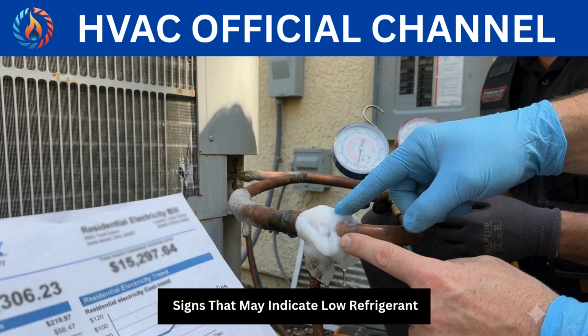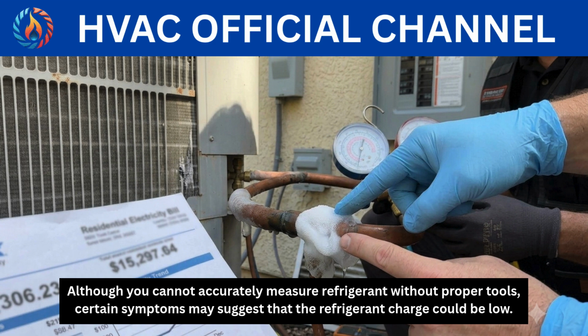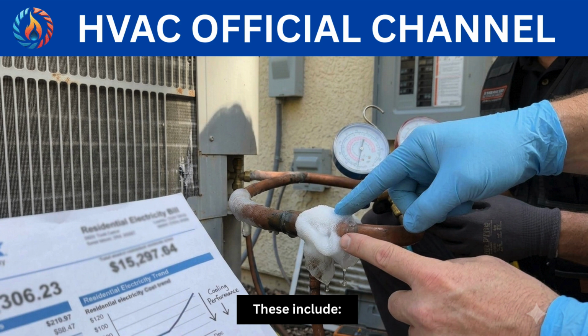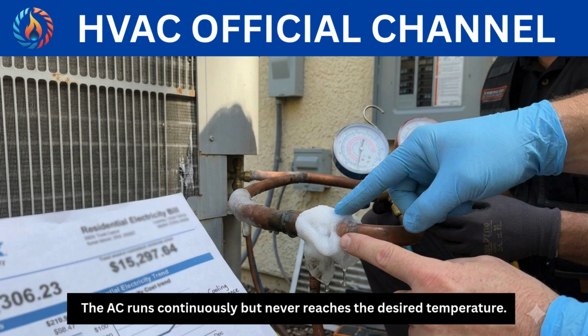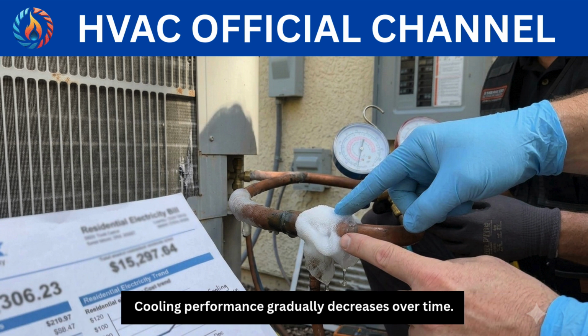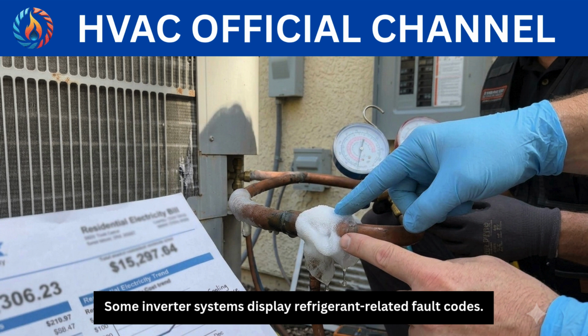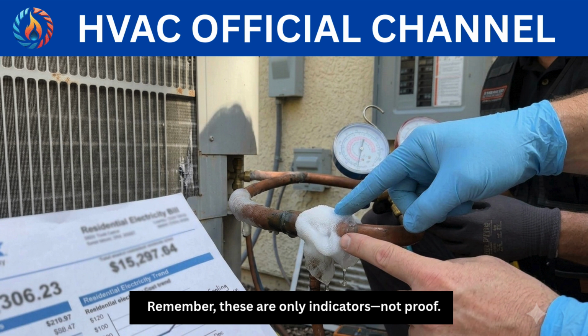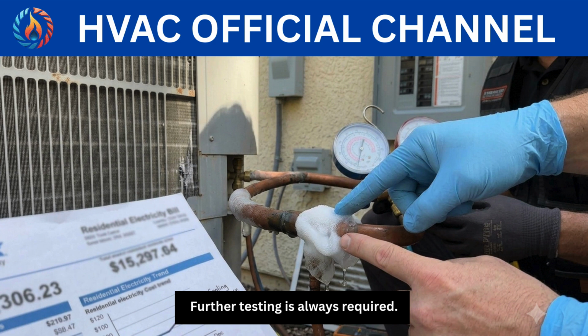Signs that may indicate low refrigerant. Although you cannot accurately measure refrigerant without proper tools, certain symptoms may suggest that the refrigerant charge could be low. These include: the AC runs continuously but never reaches the desired temperature. Cooling performance gradually decreases over time. Ice forms on the evaporator coil or suction line. The compressor runs longer than normal. The electricity bill increases while cooling decreases. Some inverter systems display refrigerant-related fault codes. Remember, these are only indicators, not proof. Further testing is always required.